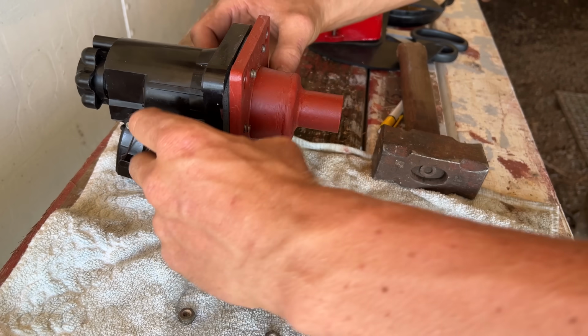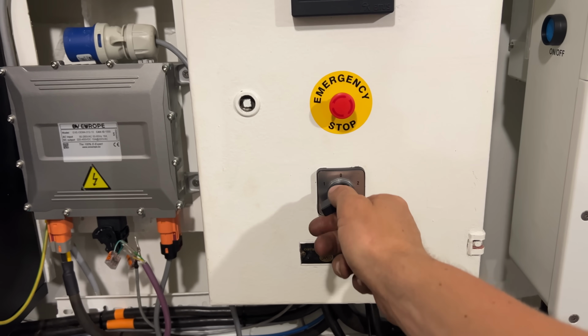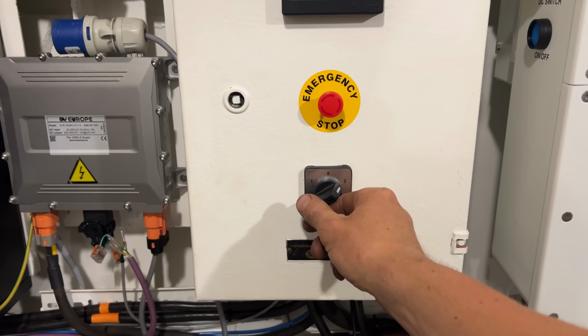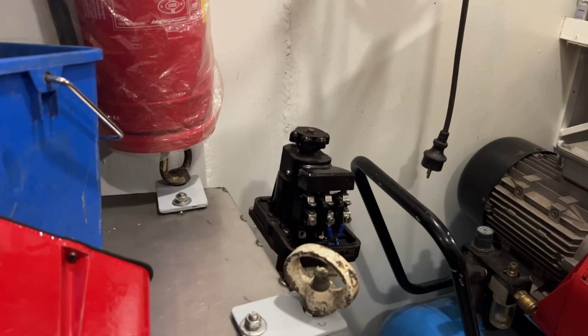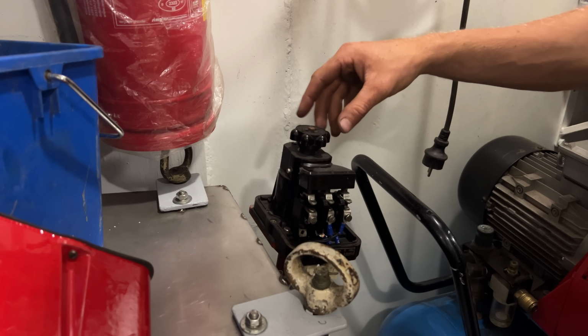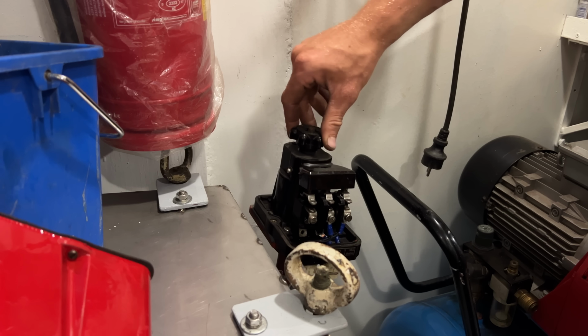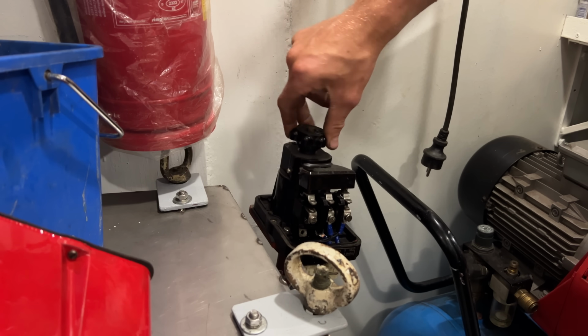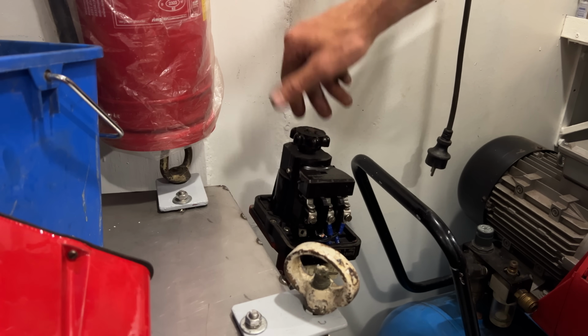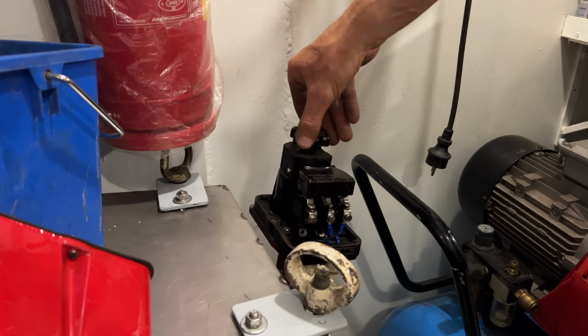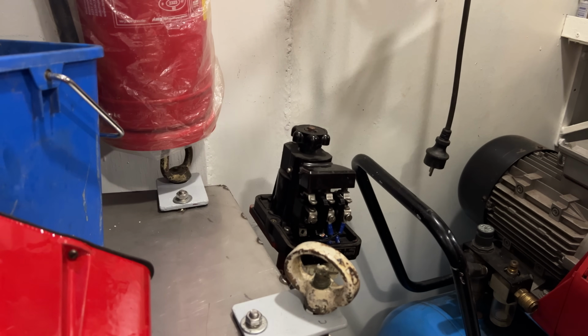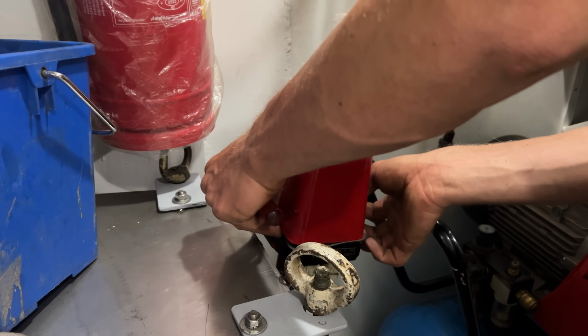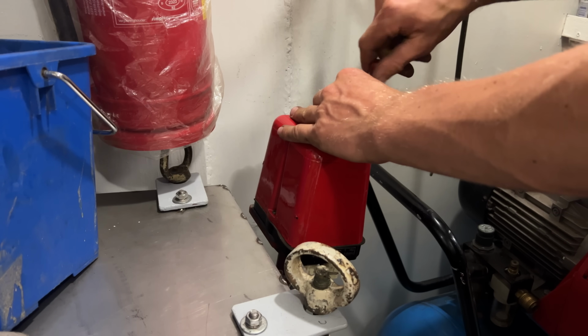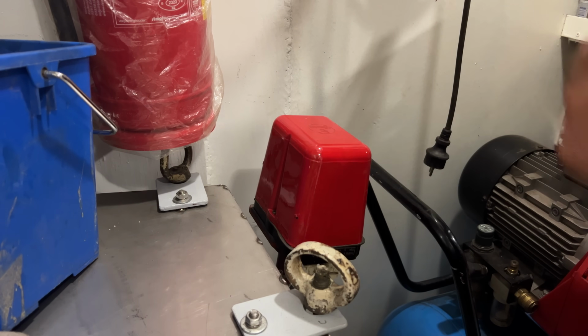To test it, we can bypass the pressure switch of the fire pump on the local cabinet. I do have to remember to make labels for this, sometime soon. The pressure can be set to a point where the pump stops when it presses against a closed line, and it starts again if the internal sprinkler head breaks. That was the last piece of safety equipment. So now we're technically safe to start using the batteries.